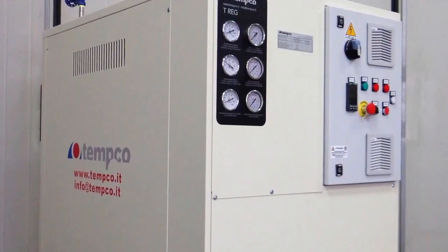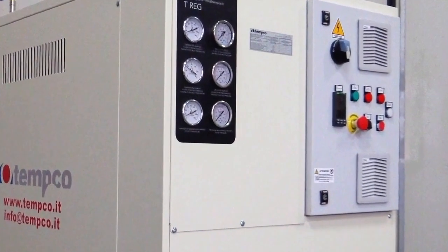Typically, this formula is utilized to analyze the various curves, the different temperature ascent and descent ramps, in order to determine which is the most demanding ascent or descent ramp. Consequently, based on this information, we can appropriately size our temperature control unit to meet the requirements of the identified ramp.